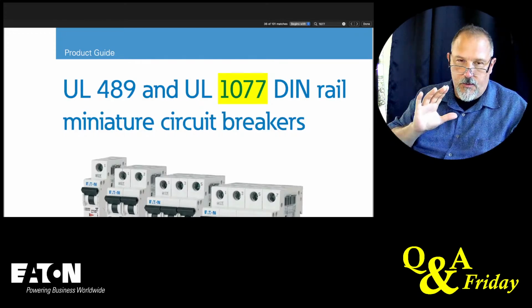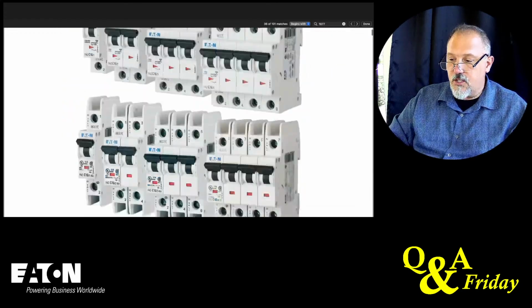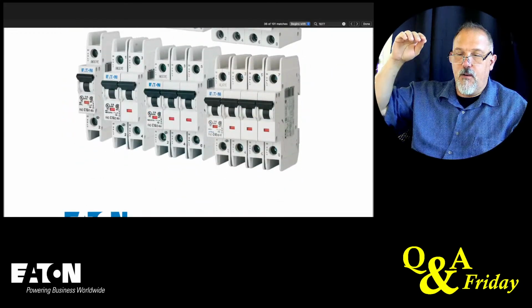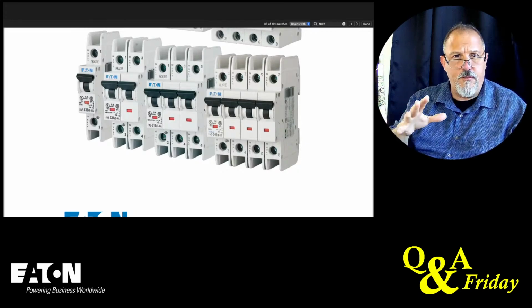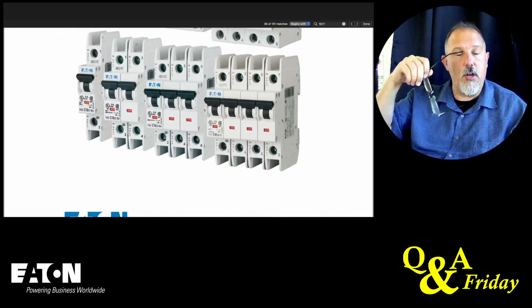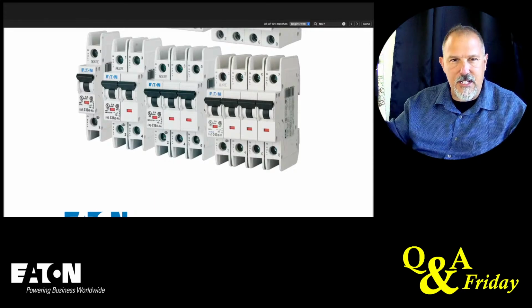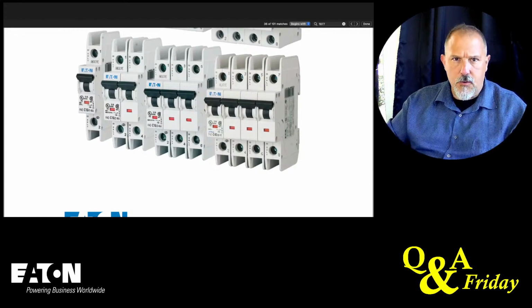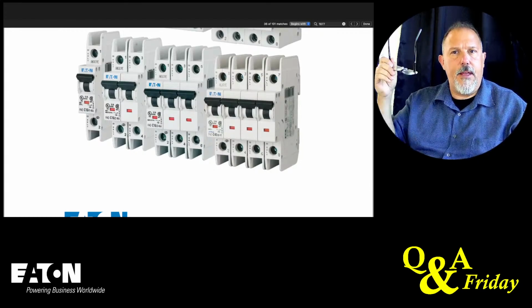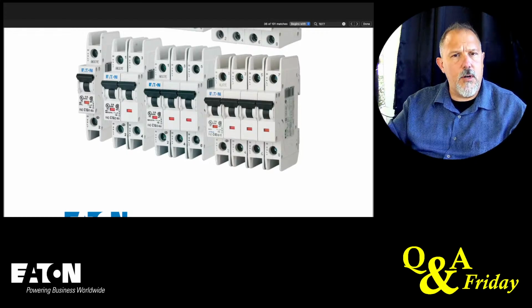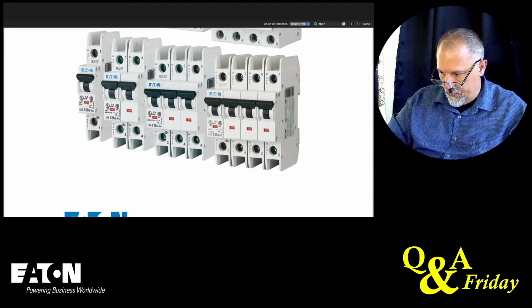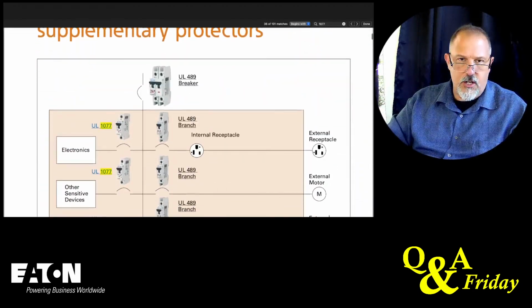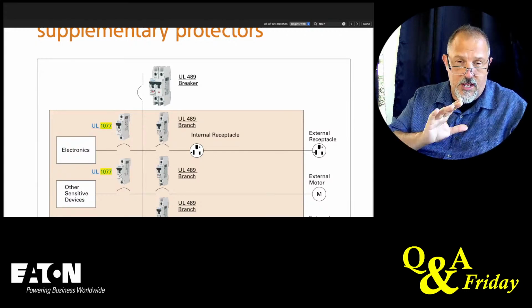So let's just scroll down, because the question is asking, from a protection perspective, we know a UL489 device is a thermomagnetic circuit breaker. So we have the overload region on a trip curve, and we have an instantaneous function. The instantaneous function acts to open high fault currents, and the overload region, that long time pickup, acts to clear overloads and lower current type of applications. So the basic question was, he's asking, first of all, what's the trip curve look like? I mean, it's the essence of his question.